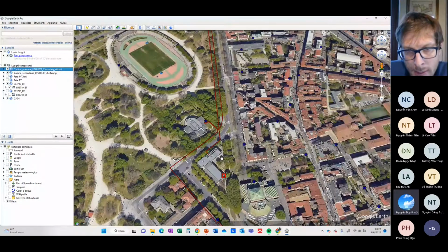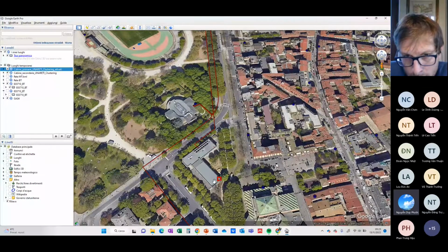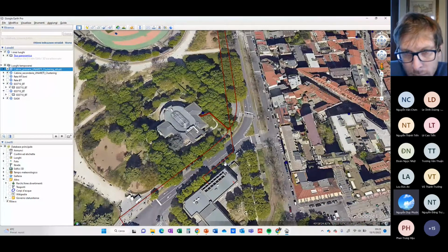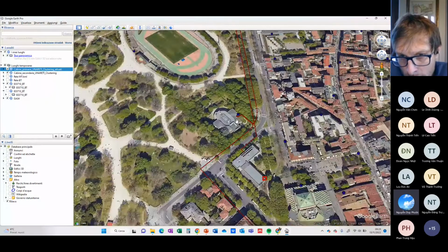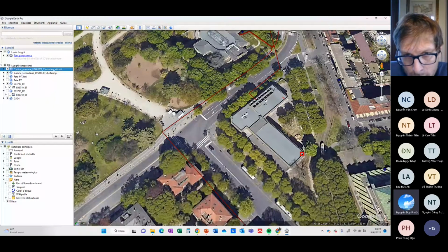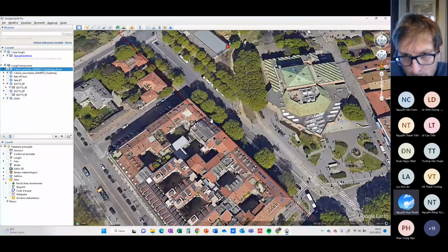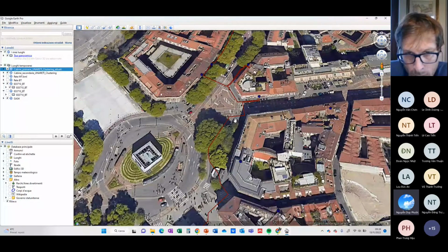let's go back to our power system. So this is a primary substation. Here the primary substation is inside this building, and from here this feeder goes out and then goes to some secondary substations. Here the feeder enters and exits, and it goes to a secondary substation, in, out, then in, out, and so on, till the end of the feeder. So this feeder is quite long, basically.